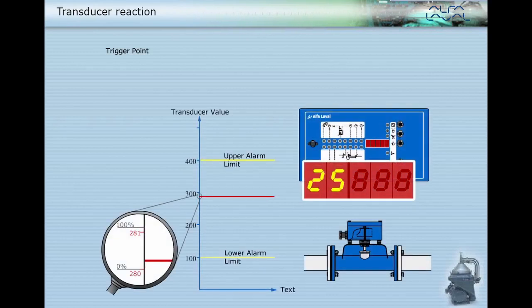When the trigger range reaches 100%, the display changes to double dash. The EPC now takes some action to reduce the water coming out with the oil. We now say it has reached the trigger point.